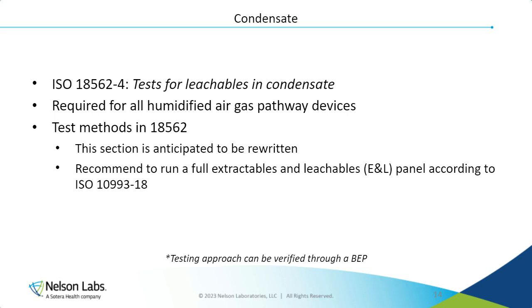ISO 18562-4 is not recognized by the FDA, as previously mentioned. So a substitute is to run a full extractable and leachable panel with the guidance of 10993-18. Additionally, the testing approach may be verified through a biological evaluation plan, which can also be done with the expert advisory services here at Nelson Labs.